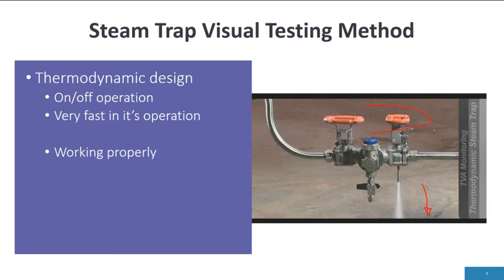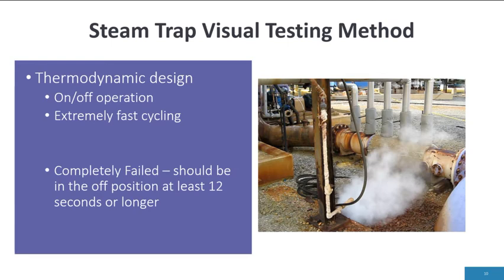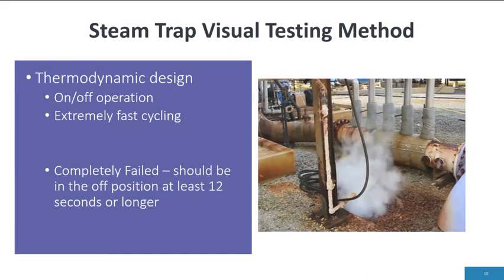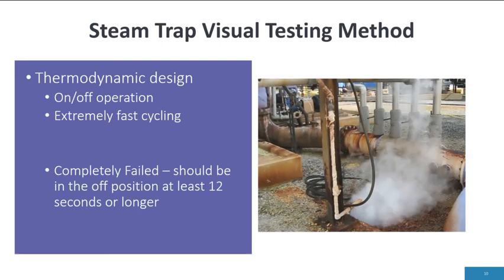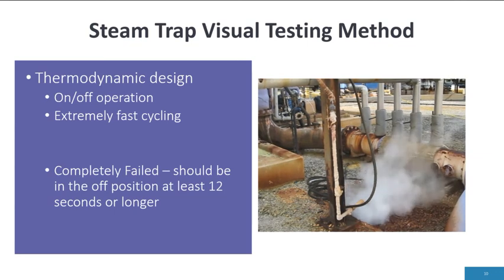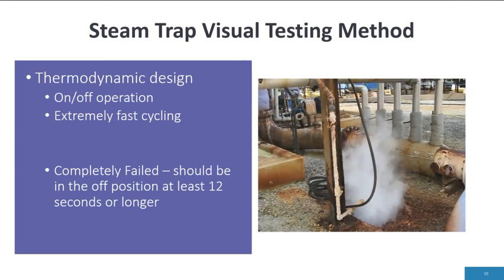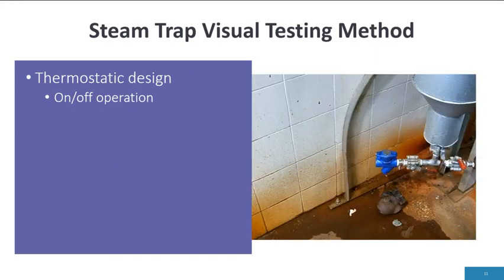This one is not working properly. If it's cycling extremely fast or completely blowing, then it has failed, and this one happens to be in the failed mode. The next type of steam trap is a thermostatic design steam trap, and this is also an on-off operation.